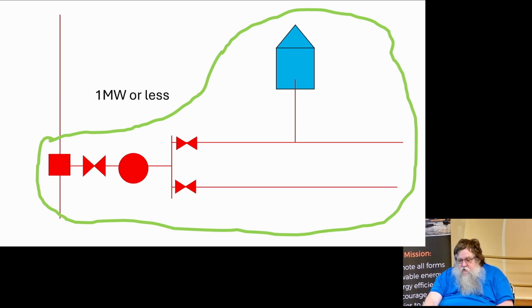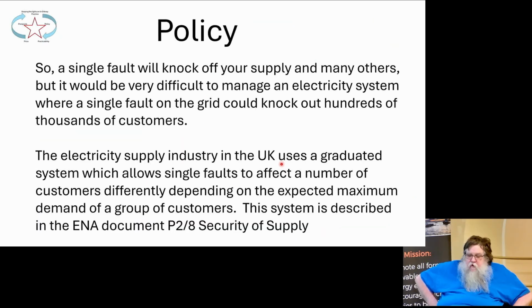So this is just a little sketch. This is a typical substation. A ring main unit at 11,000 volts, a set of fuses or a circuit breaker, a transformer, and then a low voltage bus bar with circuits feeding out, and your house is fed off one of the circuits. And we've put a green line around it. 1 megawatt or less. Typically, there is no alternative supplies. Anything of that lot that goes wrong, you're going to have to wait till it's repaired to get the power back on. Or if it's going to be a long time doing the repair, they might bring in mobile generators to get you plugged up, get the power back on for you.